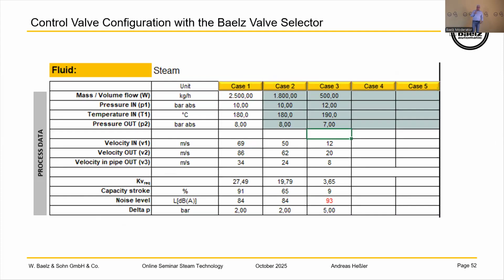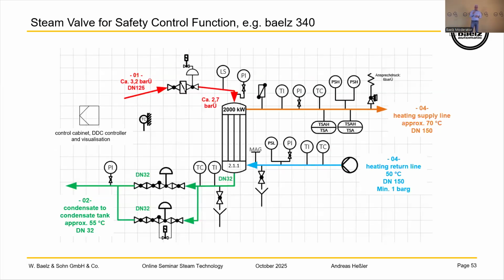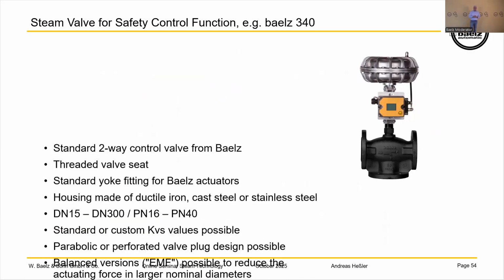Let's say something about the control valve configuration. For this, we have our BAELZ valve selector, where we can choose the correct KVS values and the correct size with the velocities, and can offer it to you. Here we have a steam valve for safety function. You see here on the top, when we have to use a steam valve for safety function, meaning quick close by over temperature or over pressure on the secondary side, we can use our valve 340.